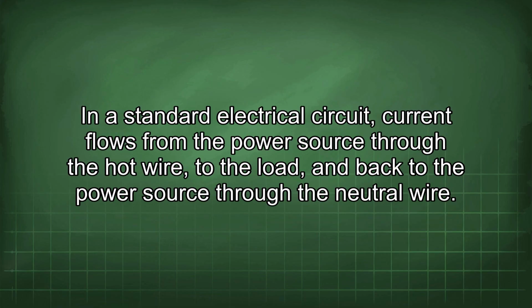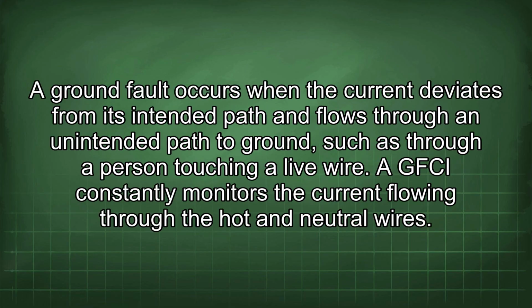In a standard electrical circuit, current flows from the power source through the hot wire to the load and back to the power source through the neutral wire. A ground fault occurs when the current deviates from its intended path and flows through an unintended path to ground, such as through a person touching a live wire.